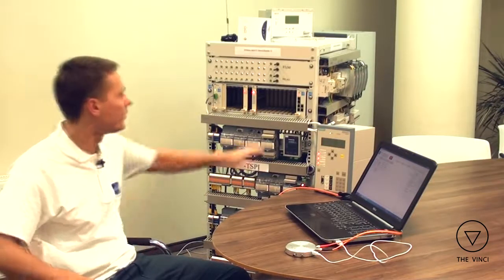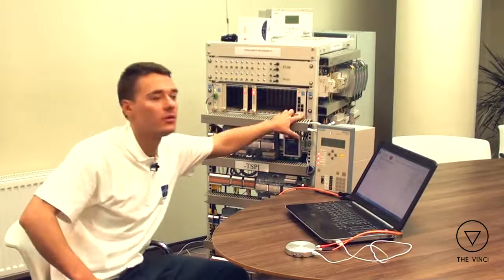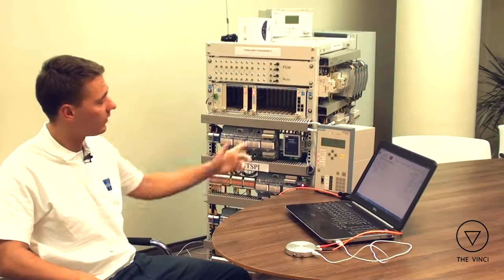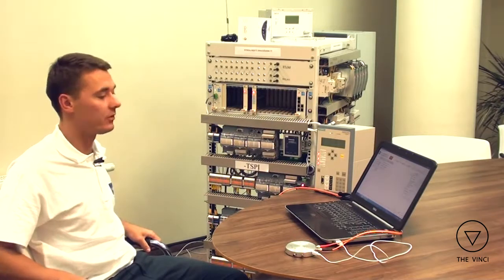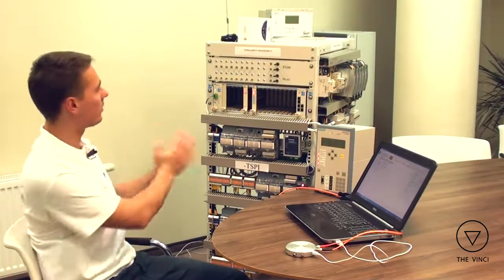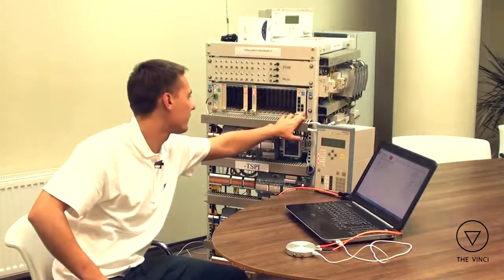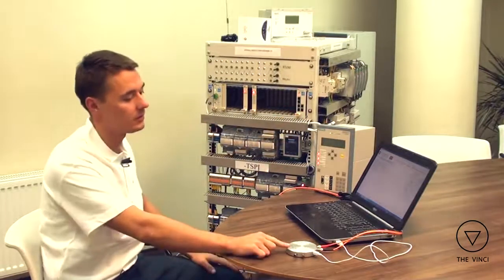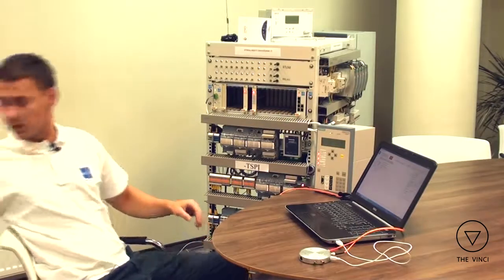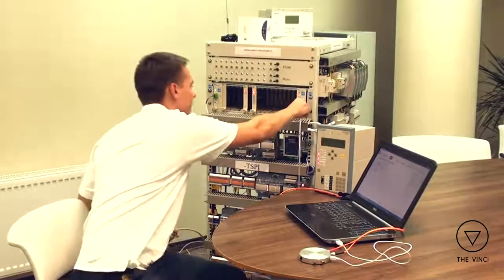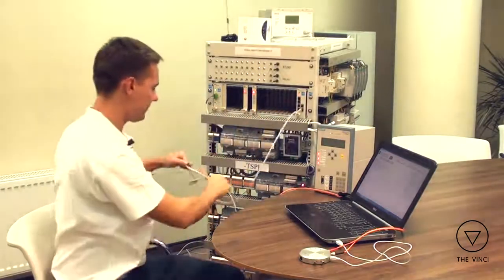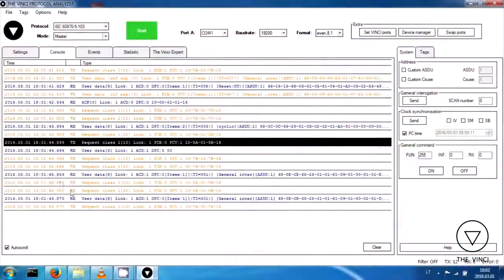In this case we have RTU560. It has RS232. And on this interface we have pre-configured 103 master. And we also have a relay. It's still fiber optics and 103 slave. So we can now connect FTP cable from the second port, RS232, to B side of this converter. So let's take a cable. Straight cable.